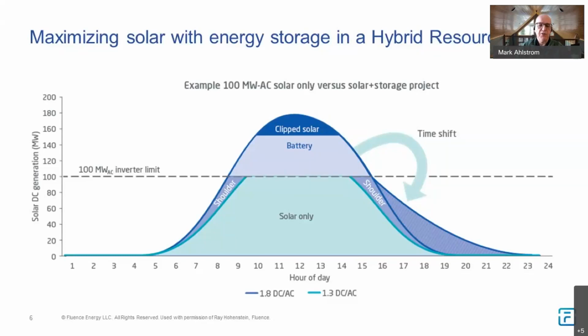And you're going to have a certain amount of energy up there that's clipped that you can't deliver to the grid, that's kind of thrown away. So what happens now, because if you are adding additional solar, say up to 1.7 or 1.8 as I'm showing here, then you end up with not only wider shoulders, which makes it a better standalone solar plant in a sense, there's more energy there, but you then get that additional peak, right?